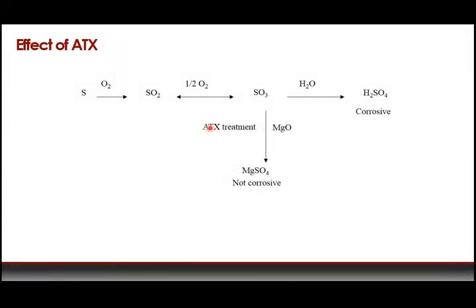The chemistry behind the action of magnesium in ATX: sulfur from the fuel oil combines with oxygen to form SO2; a certain amount reacts with additional oxygen to form SO3. Without ATX, that SO3 would eventually combine with water and form corrosive H2SO4 vapor. But if heavy fuel oil is treated with ATX, the magnesium combines with the SO3 and forms magnesium sulfate — which, unlike sulfuric acid, is not corrosive. Through this mechanism, ATX neutralizes corrosion problems.